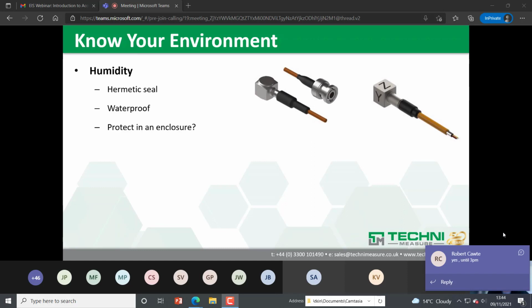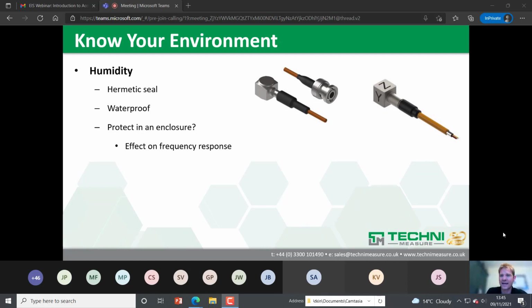Humidity, as Keith mentioned: if it's going to be in a wet environment, or even underwater, typically most test and measurement accelerometers are generally hermetically sealed. You can have waterproof accelerometers, which generally don't have connectors on them and tend to be integral lead with a sealed connection. You might consider protecting the accelerometer in an enclosure, but if you do that, just take care that the enclosure doesn't have an effect on the frequency response. That's very important.